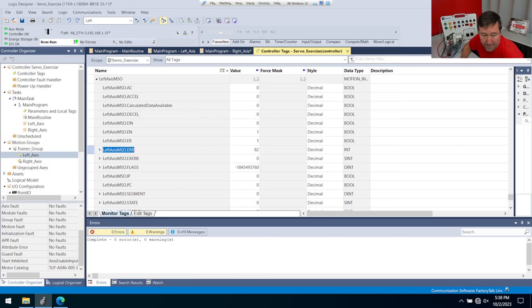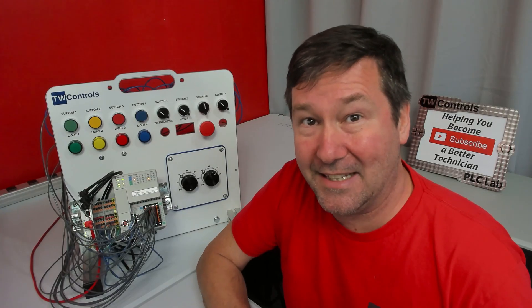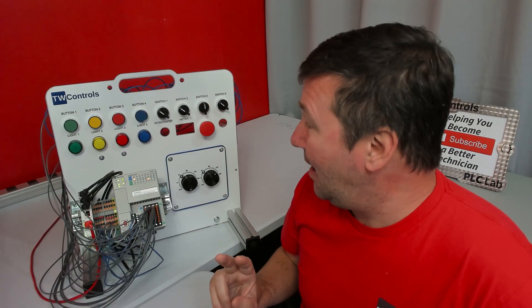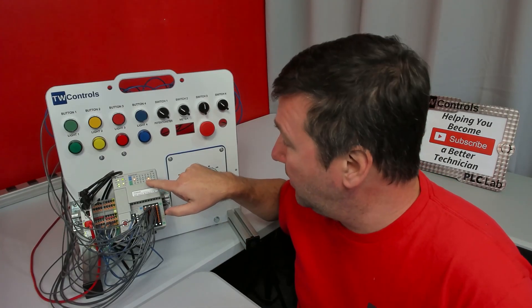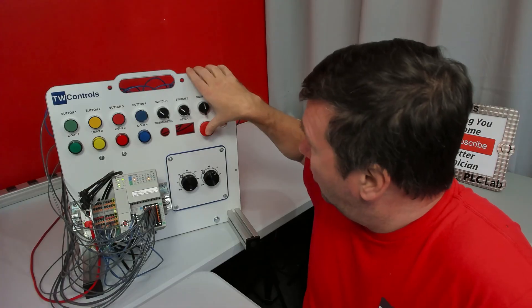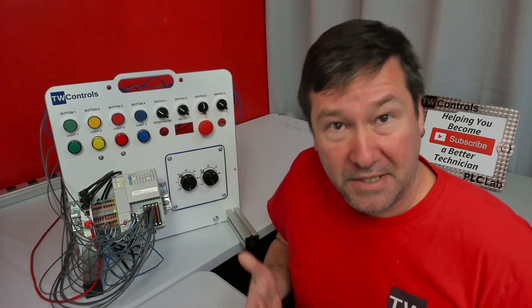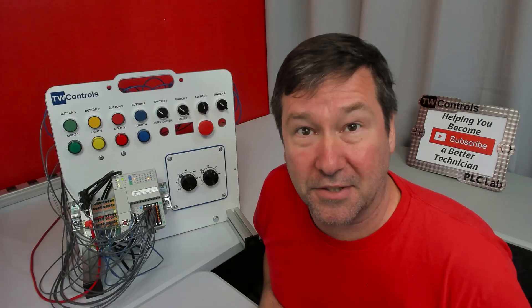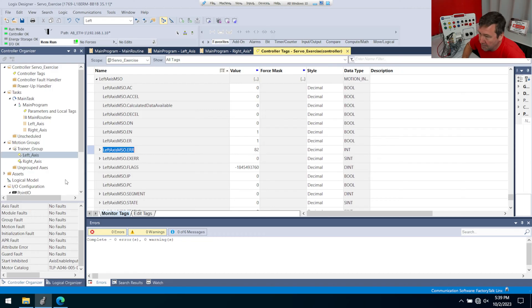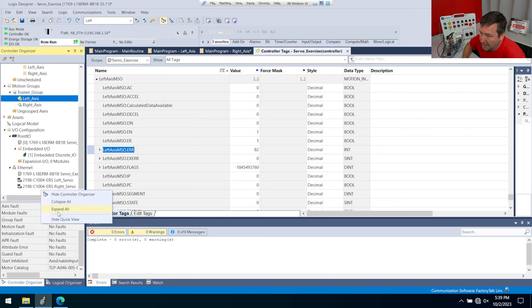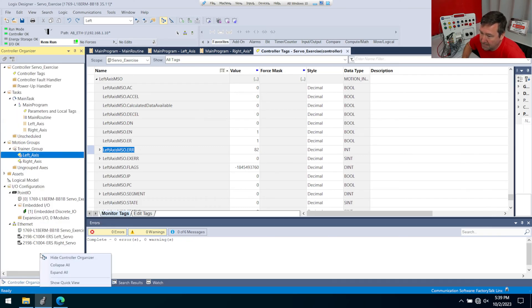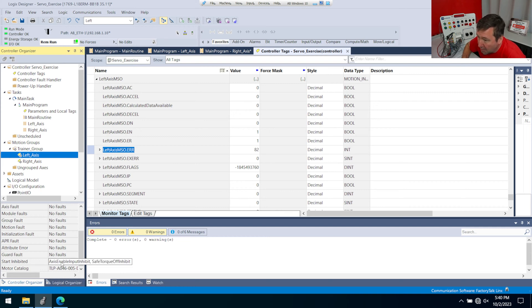It's the most common error you get. While there are many reasons you can get this error, the two most common ones are: we don't have an enable output, which is output 4, or we don't have our safe torque off, meaning something is wrong with the safety circuit. If we go into our quick view — which by default is hidden, just right-click any white space in your controller organizer and select show quick view — we have two start inhibits: the enable input coming from output 4, and the safe torque off because the red mushroom is pressed.